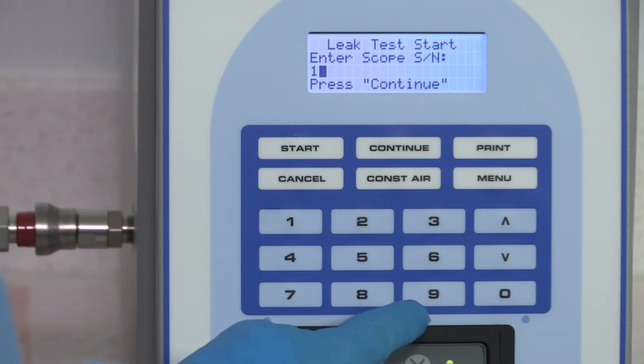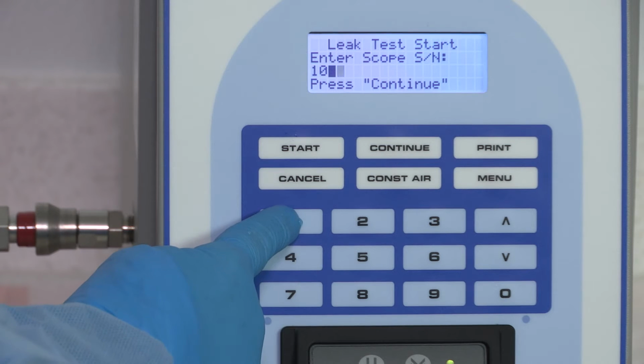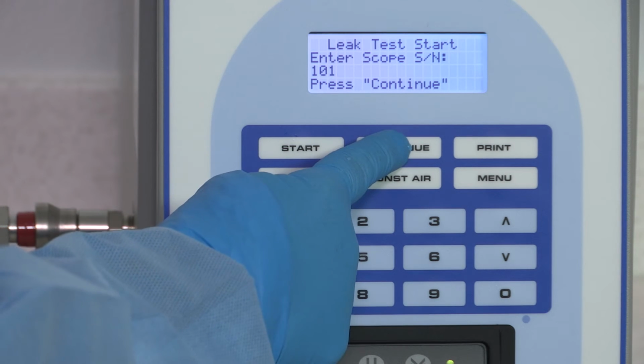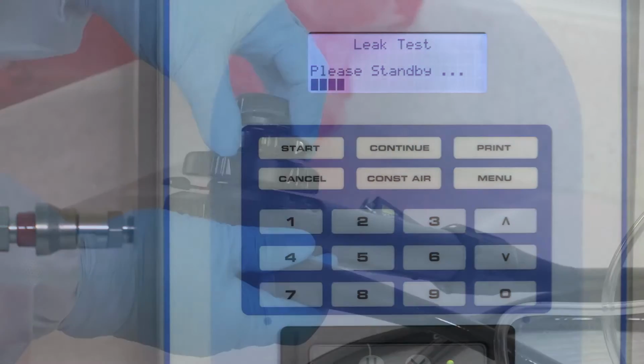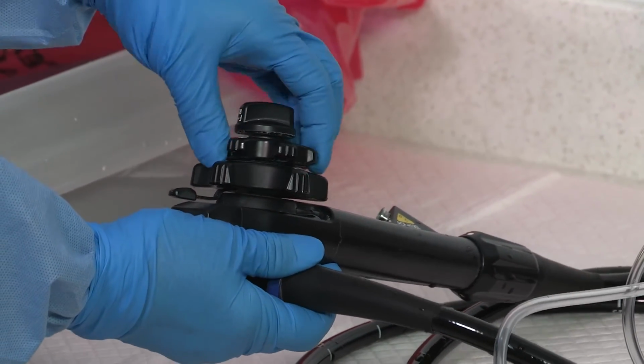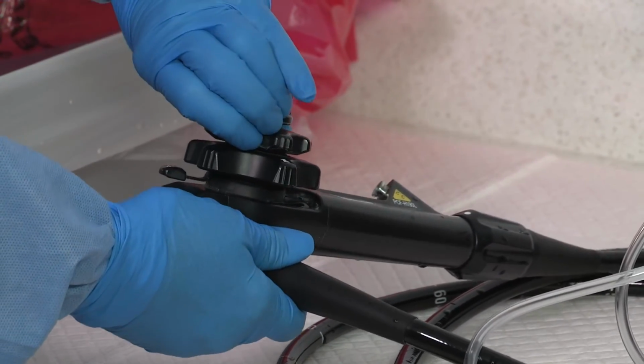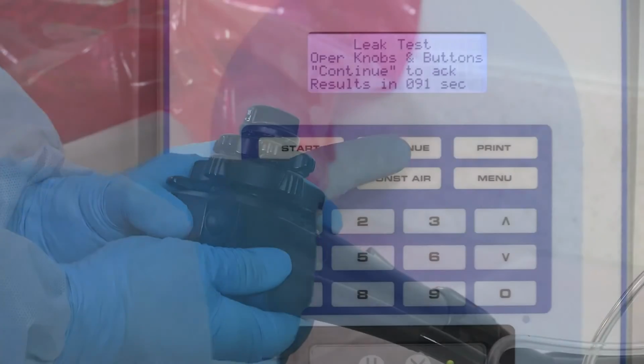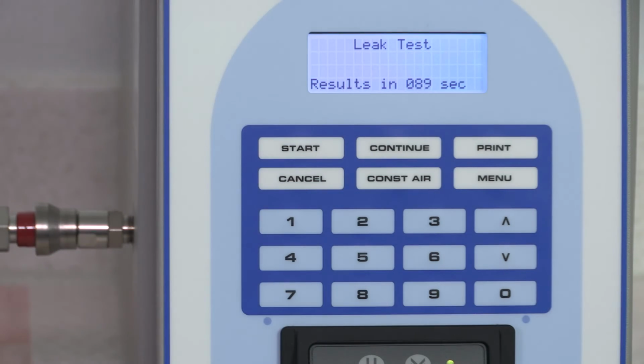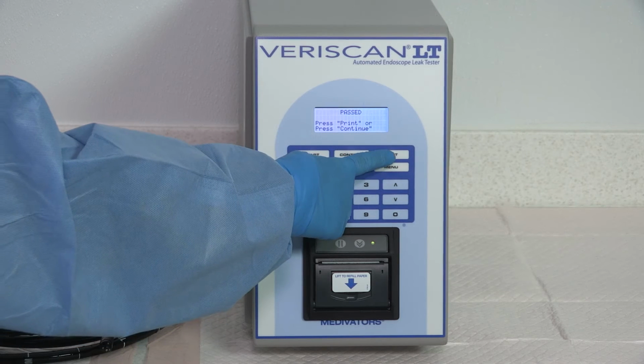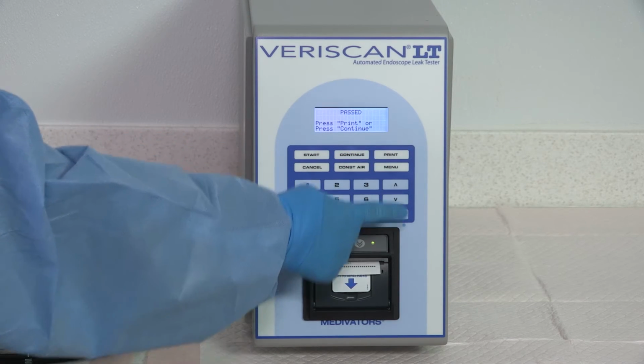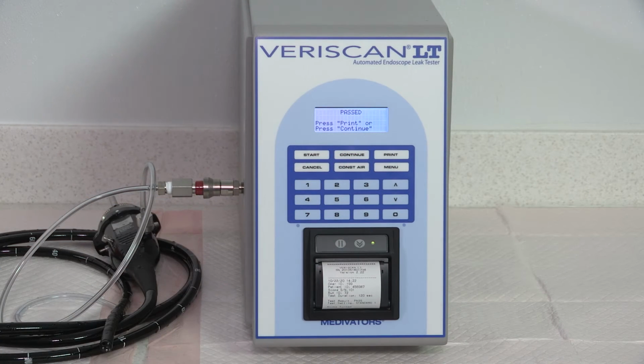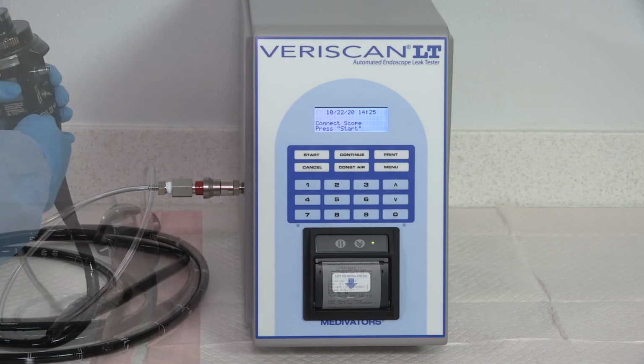Enter the endoscope serial number. Follow any additional prompts by entering the requested information. Press Continue. When the audible tone is heard, turn all endoscope angulation knobs and press all camera switches, followed by Continue. When the endoscope leak test completes, an audible tone sounds and the screen displays the pass or fail test result. If the endoscope passes the retest, then a pass result displays. Either press Print to print the results or Continue to start a new leak test.